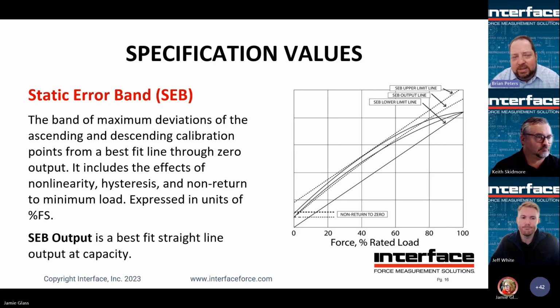And the SEB output is the best-fit straight line within that error band. We specify that SEB output on many of our calibration certificates. So again, if you're looking for an output that takes into account linearity, hysteresis, and non-return to zero, that would be the best output to use from an instrumentation calibration standpoint.